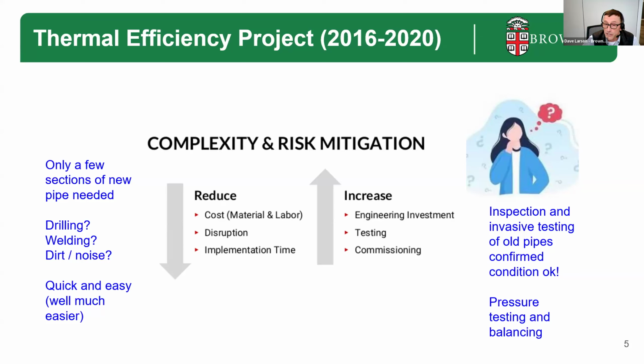There was some inspection to make sure those steam lines were adequate, including invasive testing to check the thicknesses of the pipes, and everything looked okay. We also had a contingency fund set aside in case we found pipes that needed replacing. Then pressure testing and commissioning at the end was very important.